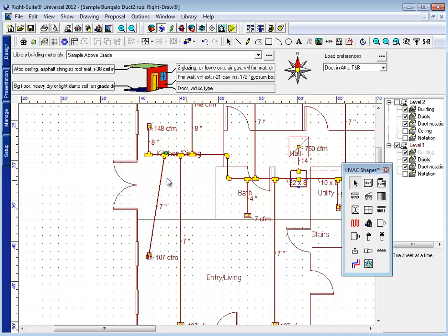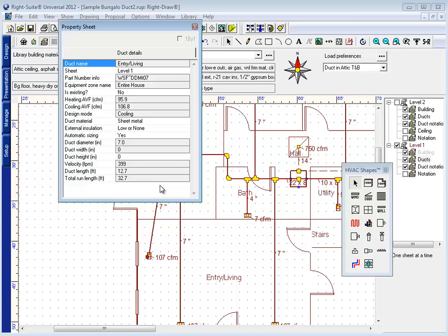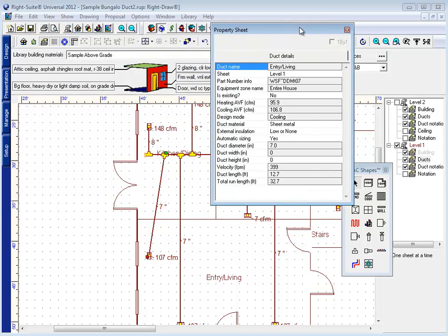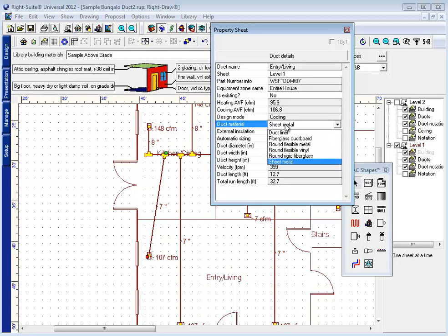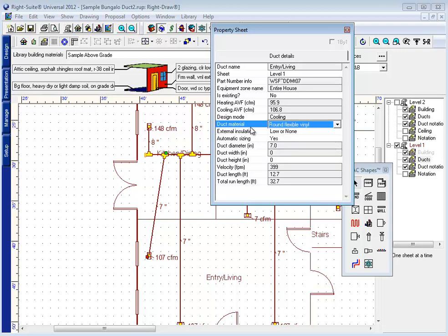Now, the problem here is I don't want all of my branch runs to become flex duct. I just want this branch run to become flex duct. So by right-clicking on that duct and that duct alone, I can look at the properties for this duct. I can see that right now it's sheet metal. If I change this property here from sheet metal to round flexible vinyl, I now have flex duct.